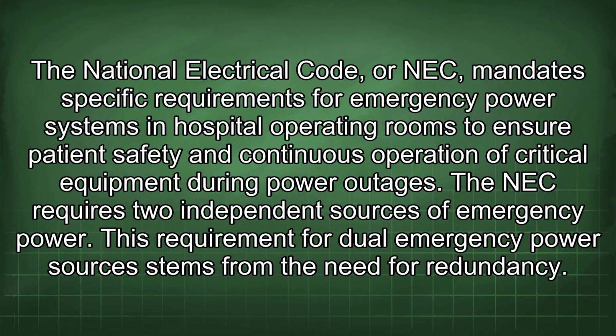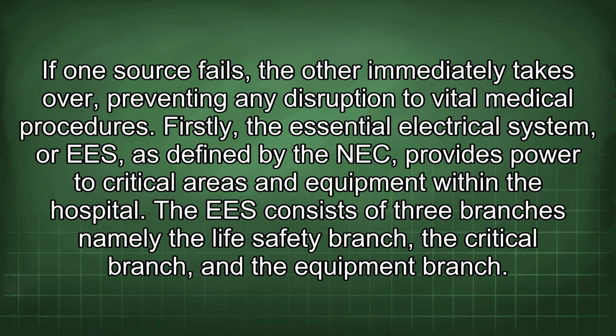The National Electrical Code, or NEC, mandates specific requirements for emergency power systems in hospital operating rooms to ensure patient safety and continuous operation of critical equipment during power outages. The NEC requires two independent sources of emergency power. This requirement for dual emergency power sources stems from the need for redundancy. If one source fails, the other immediately takes over, preventing any disruption to vital medical procedures.